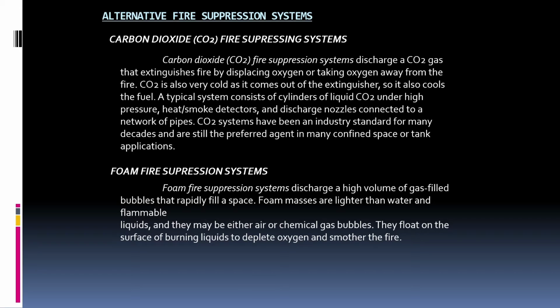There are several common applications that utilize CO2 to extinguish fires in engine compartments, deep tanks and quench tanks, and operations where spilled fuel is a possibility. The next one is foam fire suppression systems. Foam fire suppression systems discharge a high volume of gas-filled bubbles that rapidly fill a space. Foam masses are lighter than water and flammable liquids, and they may be either air or chemical gas bubbles. They float on the surface of burning liquids to deplete oxygen and smother the fire.